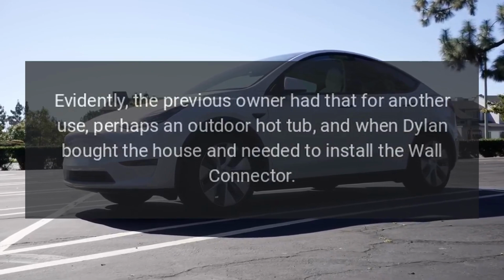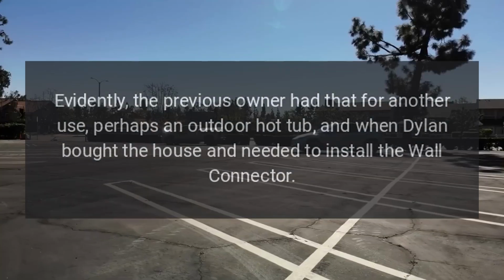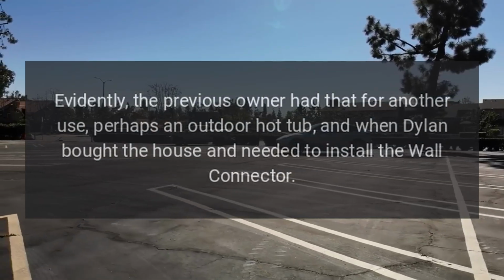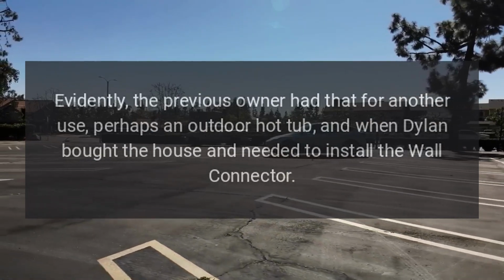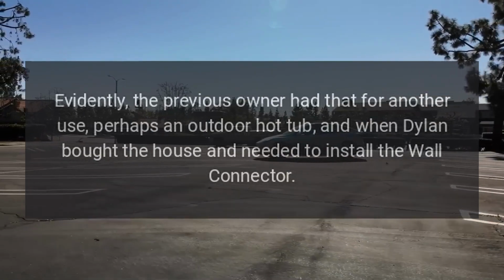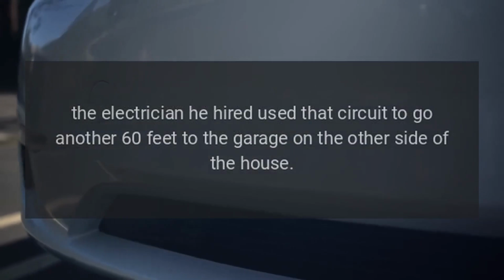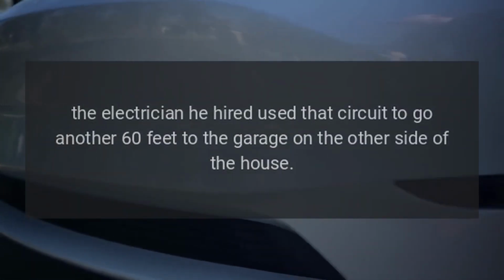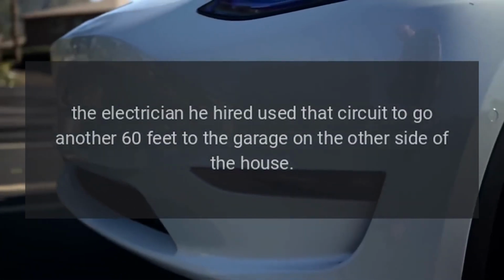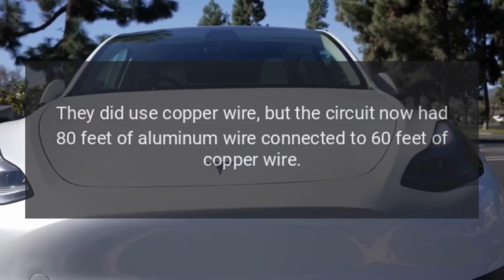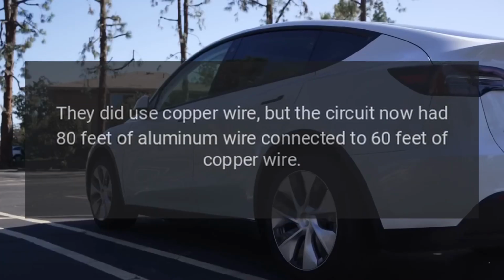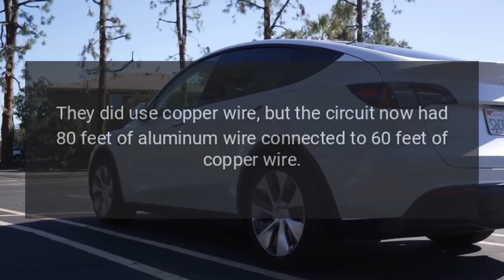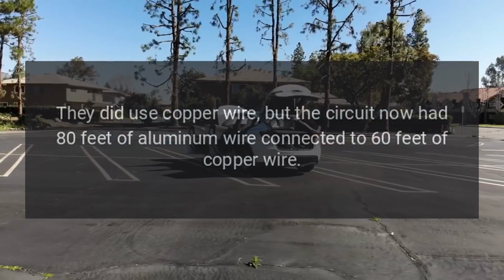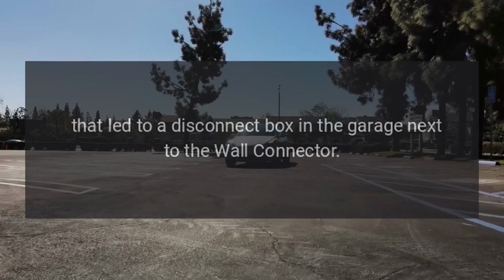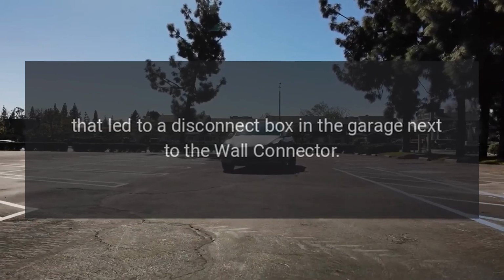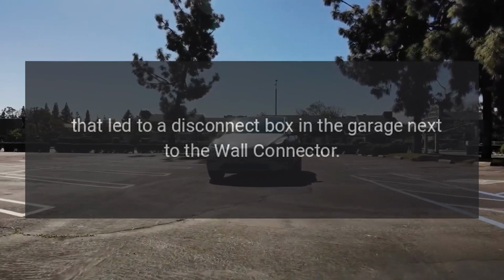Evidently, the previous owner had that for another use, perhaps an outdoor hot tub, and when Dylan bought the house and needed to install the wall connector, the electrician he hired used that circuit to go another 60 feet to the garage on the other side of the house. They did use copper wire, but the circuit now had 80 feet of aluminum wire connected to 60 feet of copper wire. That led to a disconnect box in the garage next to the wall connector.